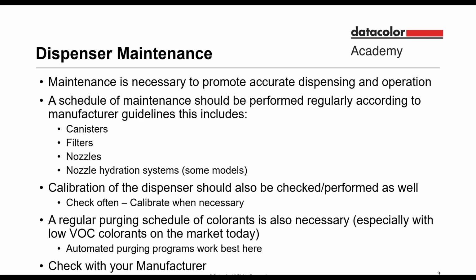So some guidelines included in maintenance, depending on the type of dispenser that you have. We're going to talk more about automatic dispensers as opposed to manual dispensers. Canister filling and cleaning is important. The cleaning of filters is also important. Making sure that your nozzles are clean and free of dried pigment, as well as your nozzle hydration or humidification systems. Some models have an auto cap where there's a sponge in there that has liquid in it to keep the tips moist. Other systems have a more complex humidification system that's more automated that pumps liquid past the actual nozzles to keep them moist as well.